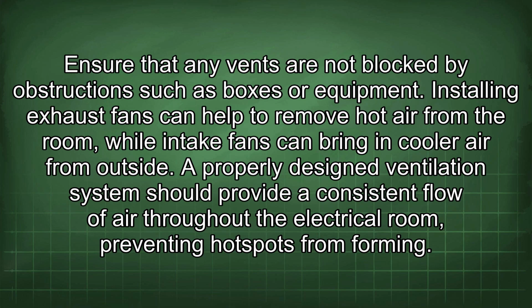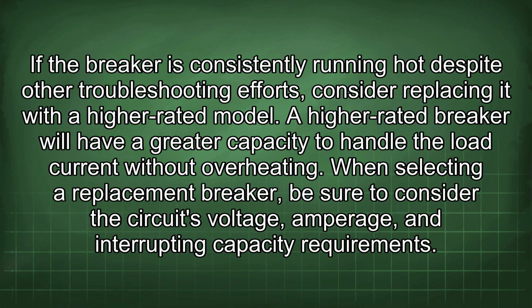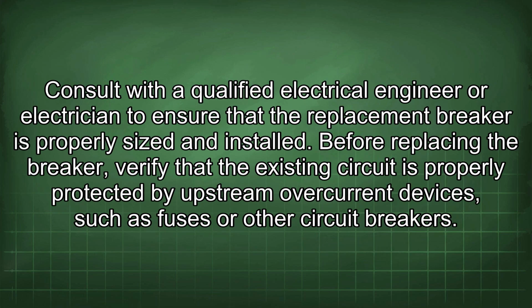from forming. If the breaker is consistently running hot despite other troubleshooting efforts, consider replacing it with a higher rated model. A higher rated breaker will have a greater capacity to handle the load current without overheating. When selecting a replacement breaker, be sure to consider the circuit's voltage, amperage, and interrupt capacity requirements. Consult with a qualified electrical engineer or electrician to ensure that the replacement breaker is properly sized and installed.